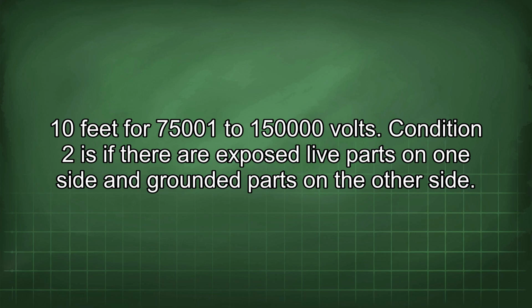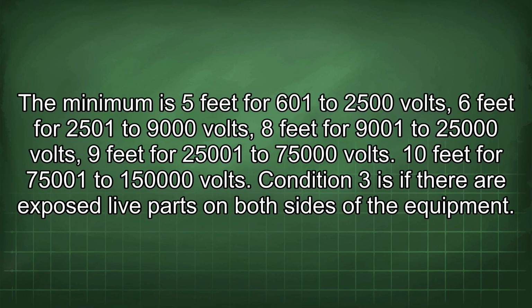Condition 2 is if there are exposed live parts on one side and grounded parts on the other side. The minimum is 5 feet for 601 to 2500 volts, 6 feet for 2501 to 9000 volts, 8 feet for 9001 to 25,000 volts, 9 feet for 25,001 to 75,000 volts, 10 feet for 75,001 to 150,000 volts.